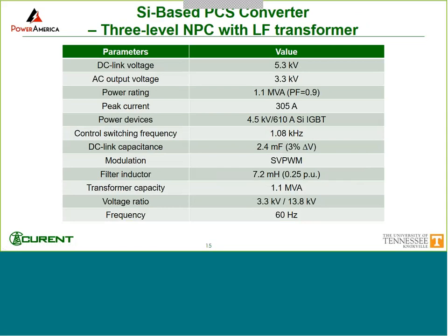Then we carried out the design specifically for each of the architectures I have shown. So this is the silicon case, with the DC link voltage, AC output voltage, and power rating. The power ratings are the same. This is the selected devices and the switching frequency. This is really the control switching frequency, right? Because for the NPC, the individual device switching frequency is lower. The DC cap selection is based on 3% voltage ripple, then the modulation strategy, and because of the system requirement, the filter inductor, and the transformer turns ratio.